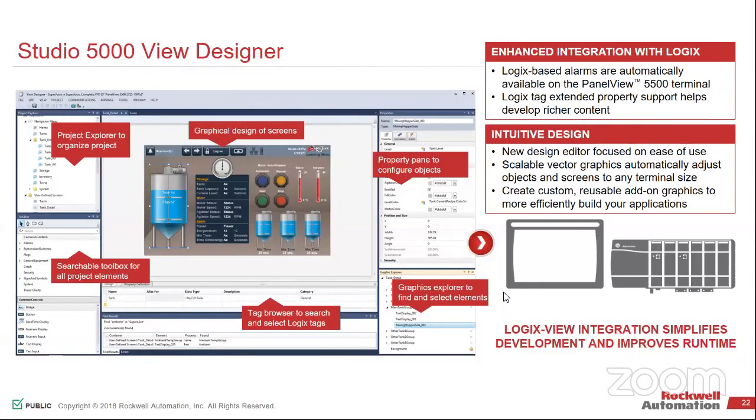It uses vector graphics, and more importantly, it's the tightest integration we have with Studio 5000 or the Logix controllers. Everything is native to it on the tag browsers. The limitation is that it does not support third-party products. So if you need to run Modbus back to it, that's not available. It's not going to be available. This is strictly a Logix-based HMI. It will be our most cost-effective one in the future for a standalone, purpose-built HMI.